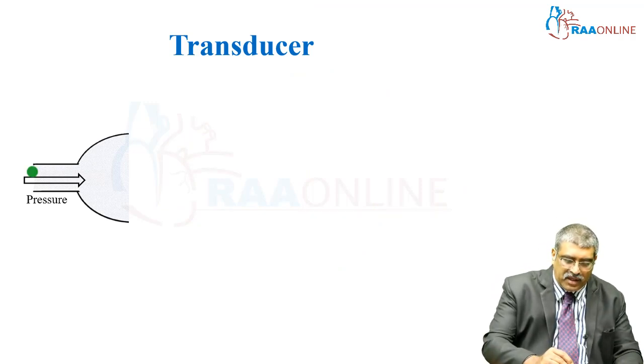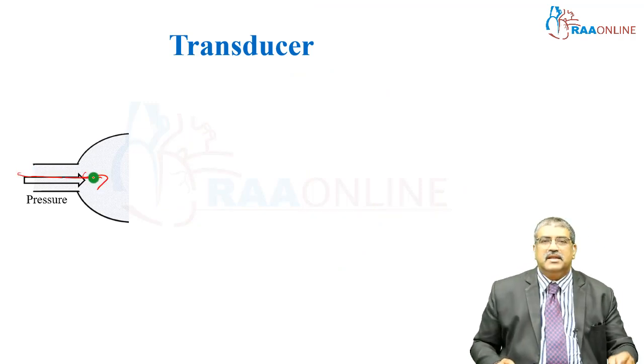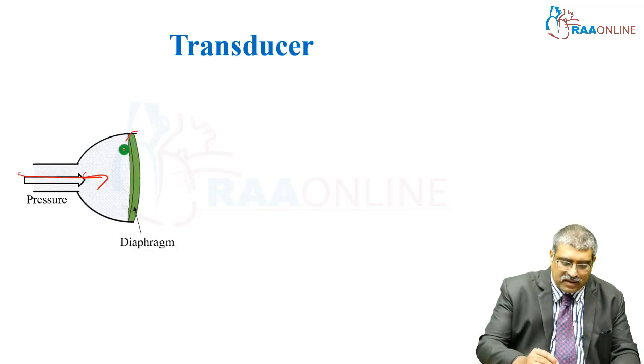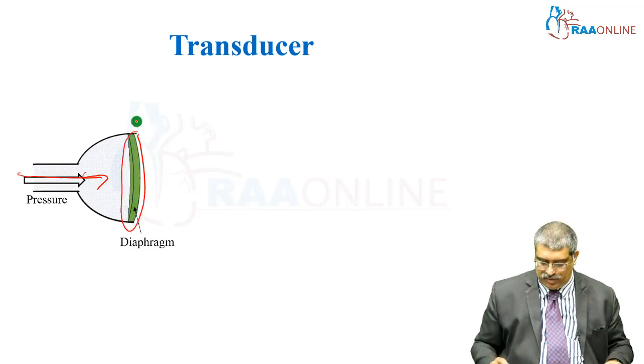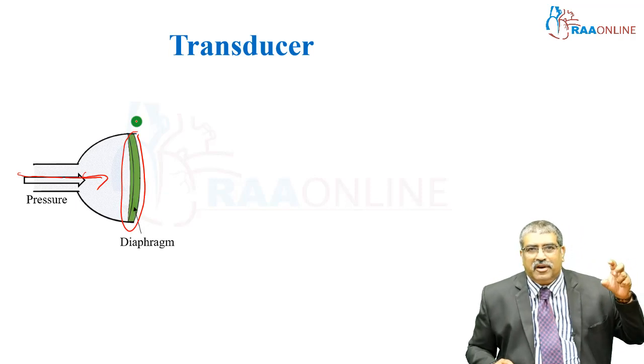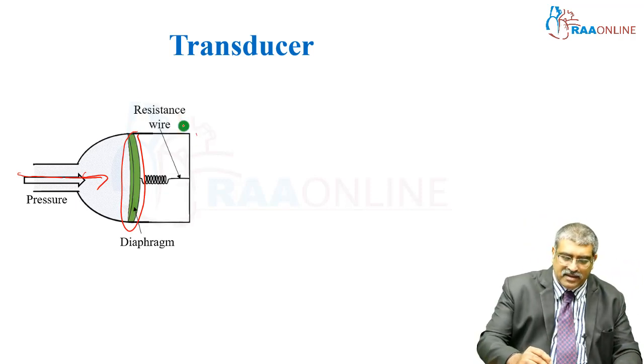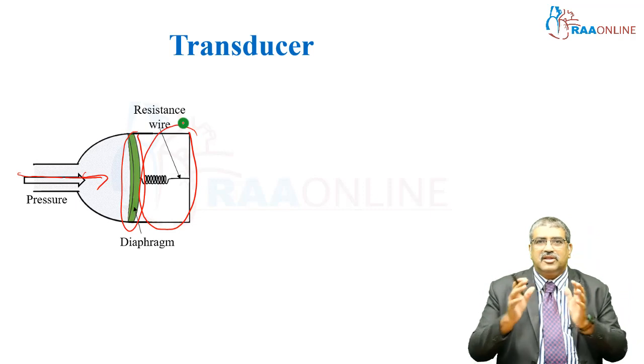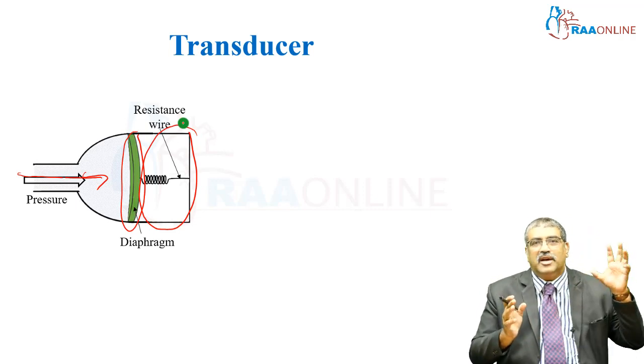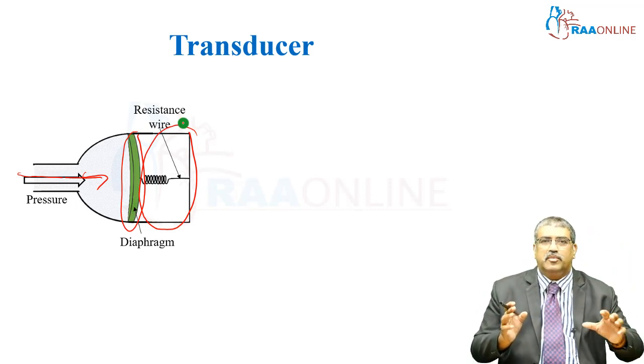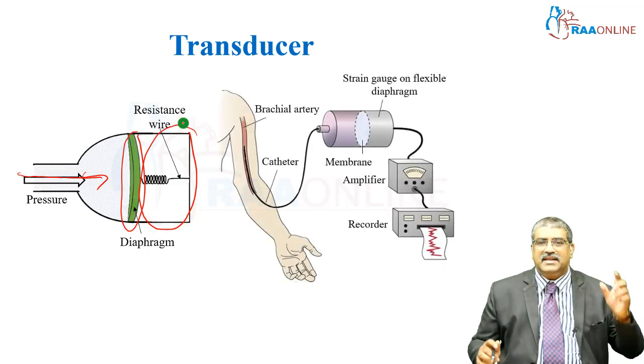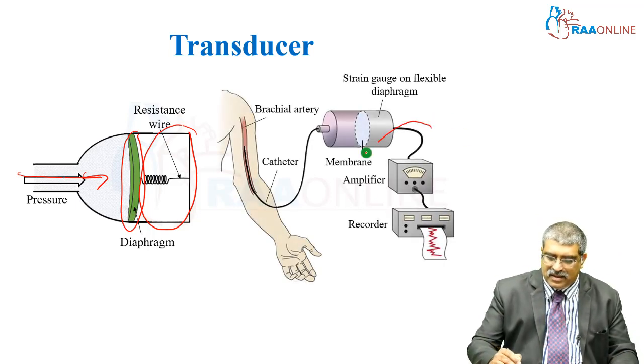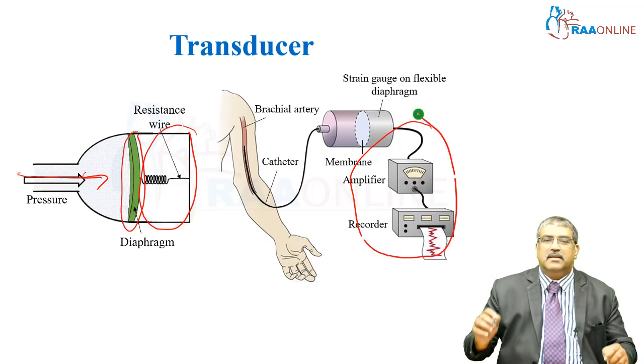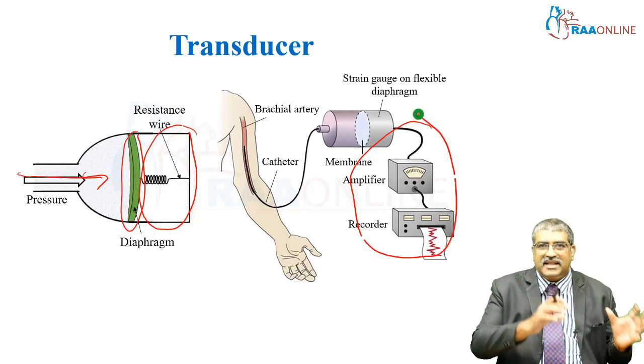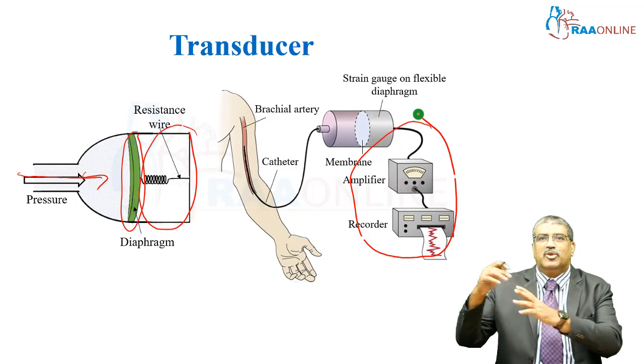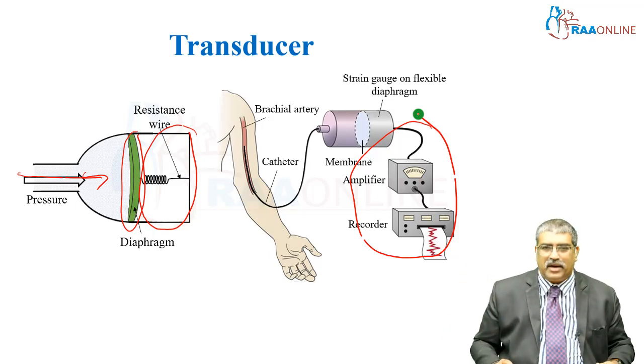The pressure from the arterial line is transmitted to the diaphragm in the transducer. As the diaphragm gets pressure altered, the resistance inside the circuit of the transducer is altered, and that is where your strain gauge and Wheatstone bridge come into picture. As it gets altered, there is an amplifier to take this electrical signal into a digital format.